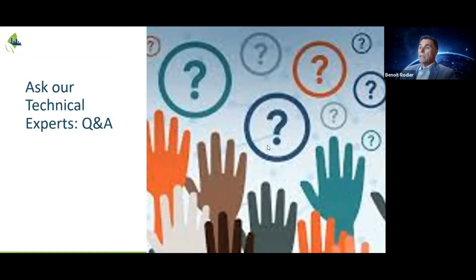I can take the next question on CO2. What we're seeing in the market is actually not pushback but more interest in replacing systems with CO2 systems. In Quebec, for example, 80% of the R22 systems that have been replaced were replaced with CO2 systems. So to put things in perspective, nothing is perfect - no refrigerant is the perfect solution. Synthetic refrigerants have a strong impact on global warming potential, so they're not the right solution environmentally.